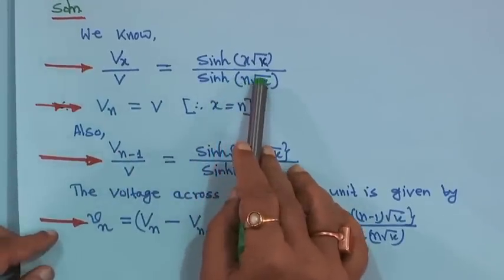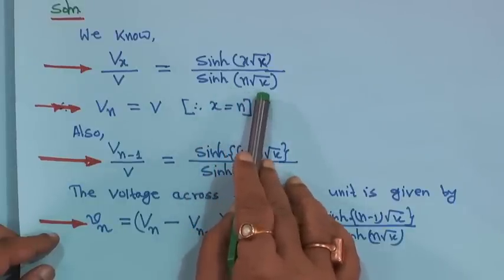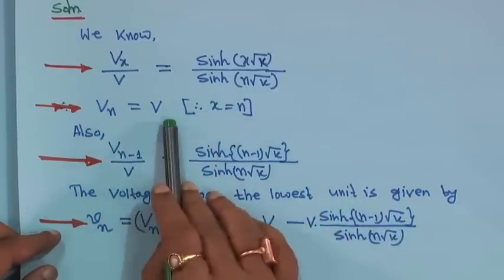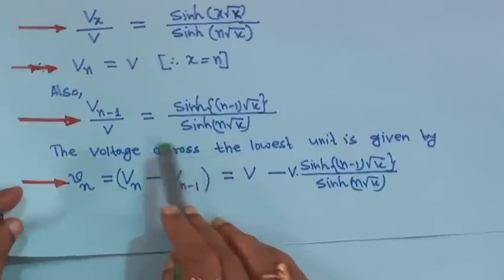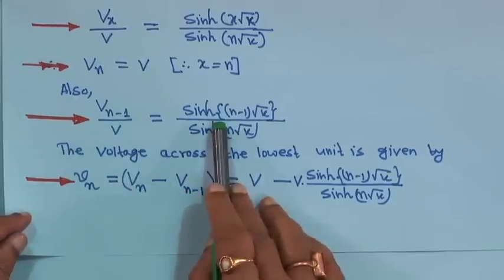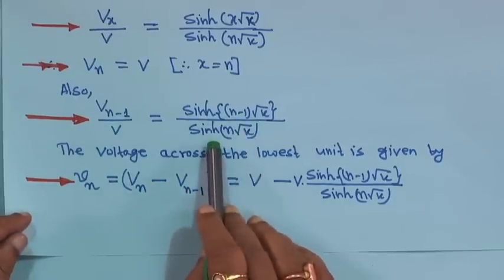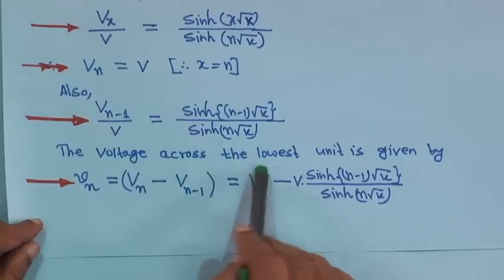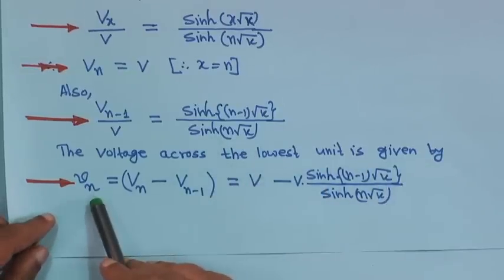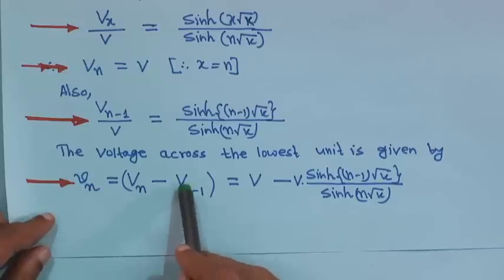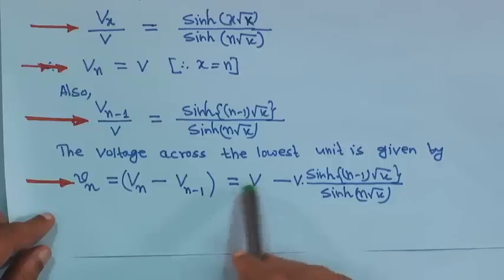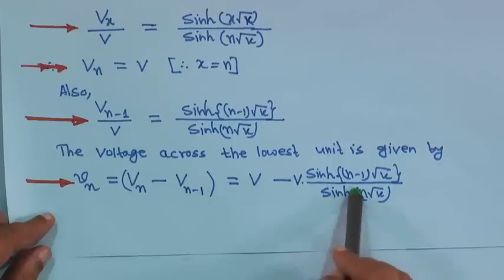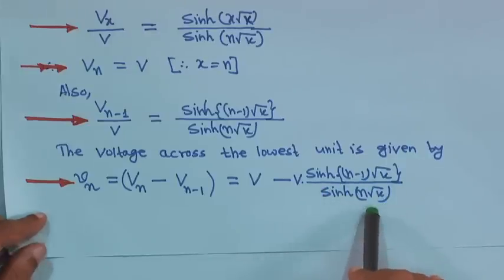We have already derived that V_x upon V is equal to sinh(x√k) divided by sinh(n√k). For x equal to n, V_n is equal to V. Therefore, we can write V_(n−1) upon V is equal to sinh((n−1)√k) divided by sinh(n√k). The voltage across the lowest unit is given by small V_n equal to capital V_n minus capital V_(n−1). Substituting: V_n equals V minus V times sinh((n−1)√k) divided by sinh(n√k).